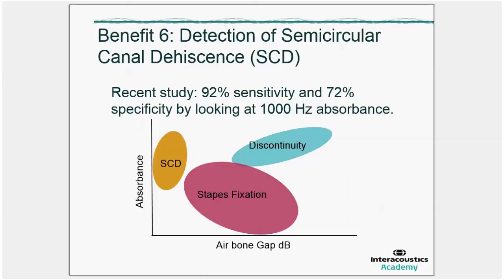Let's go to the question that was just asked. In case of a perforated ear, will you not use an absorbance measurement without applying pressure? If the ear shows a perforation, then if it is safe to do the measurement, then you do not need to stick at ambient pressure. Of course, you can do the measurement at ambient pressure only. And when you do the pressurized measurement, the measurements at all pressures will appear approximately the same. If you know that there is a perforation, then maybe it is easiest to just do the ambient pressure measurement.